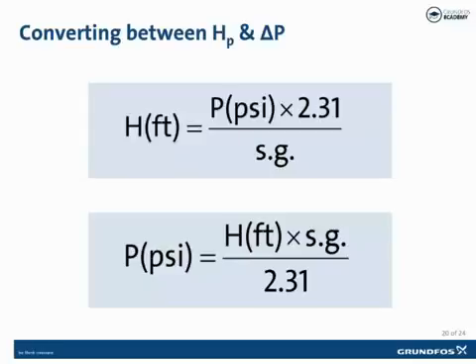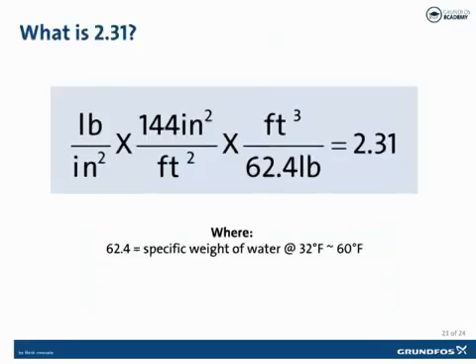To convert from head to PSI: head times the specific gravity of the fluid divided by 2.31 gives you PSI. The specific gravity of water is 1.0. The figure of 2.31 is derived from the specific weight of water. Since we calculate pressure in pounds per square inch, and there are 144 square inches in one square foot, and the weight of water between 32 and 60 degrees Fahrenheit is roughly 62.4 pounds per cubic foot, we multiply 144 divided by 62.4, which gives us 2.31.